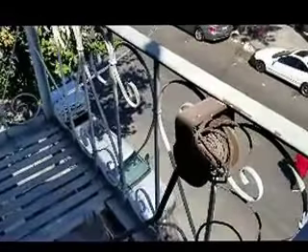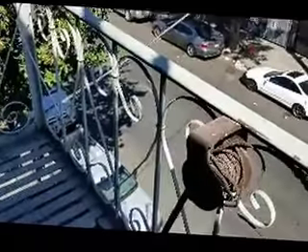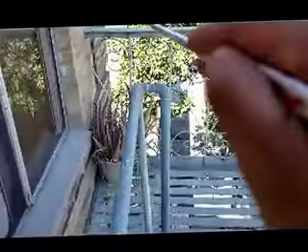At this point, I'm here at the highest level of this fire escape system. This is the highest platform of this fire escape system. This is actually the 3rd level. So this is the 3rd level platform. However, it's considered the 2nd platform, since there are only 2 platforms. So as you can see, the connection to the building appears to be okay, with slight cracks that we want to go ahead and further investigate.